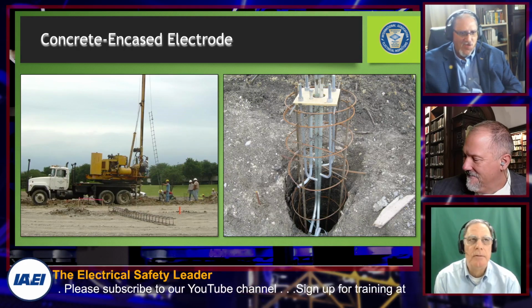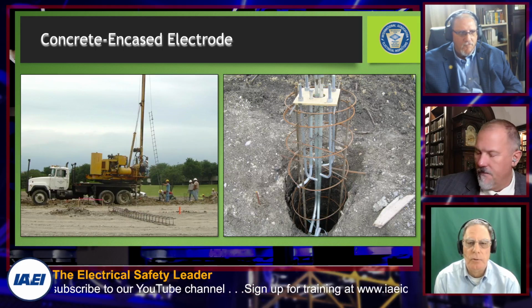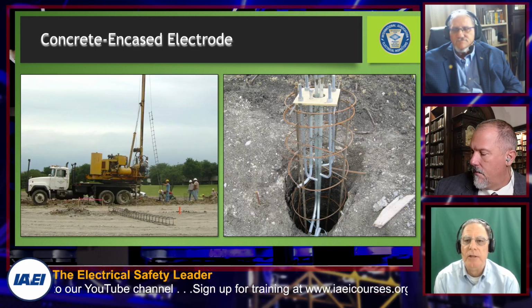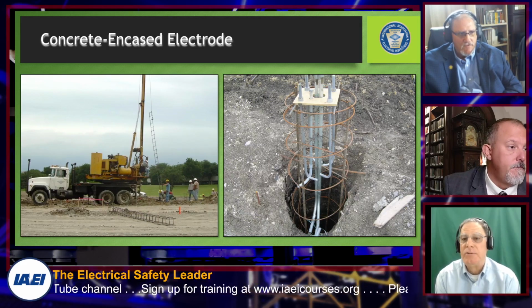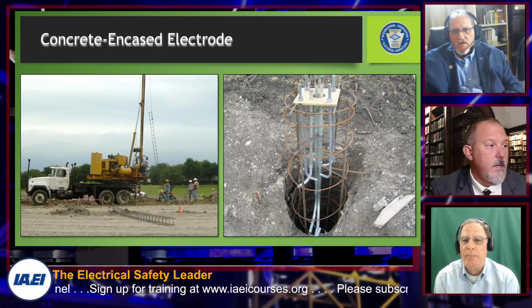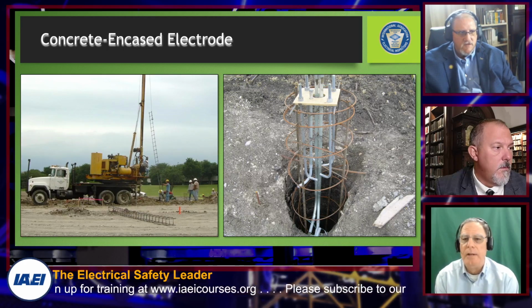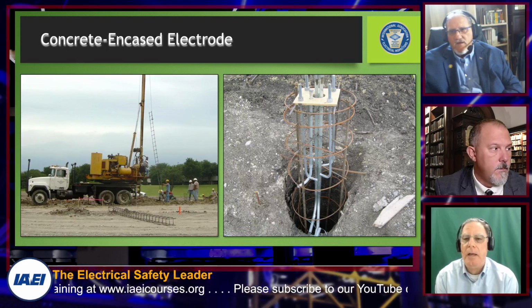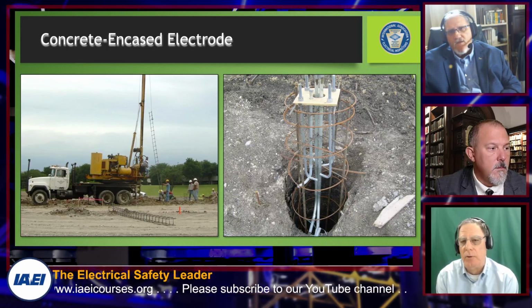Probably the other thing that comes up a lot with concrete encased electrode is when they put vapor barriers or insulation in and around the concrete so it's not in direct contact with the earth. People think if they got rebar in the concrete, it's a concrete encased electrode. It's not, because it doesn't meet that direct contact with the earth requirement.